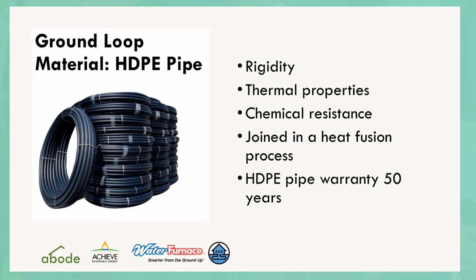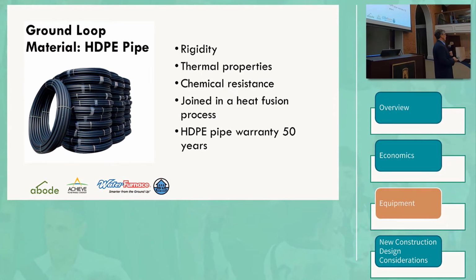Ground source installs, the ground heat exchangers are always constructed of high-density polyethylene piping, specially selected for geothermal based on their thermal properties, chemical resistance, and the mix of rigidity and flexibility. The piping is joined with a heat fusion process. There are no mechanical connections, so you're not screwing anything together. There are no wrenches. Everything is melted together, and it's a very reliable, long-lived technology for piping. When you see them putting in the gas lines on the street, that's the same high-density polyethylene pipe. It just happens to have a yellow jacket on the outside to identify it as gas, and that's all thermally welded, just like our stuff.